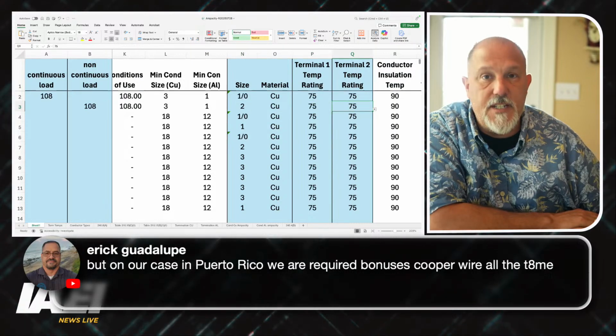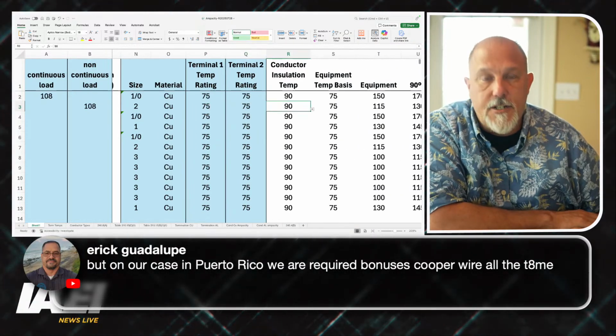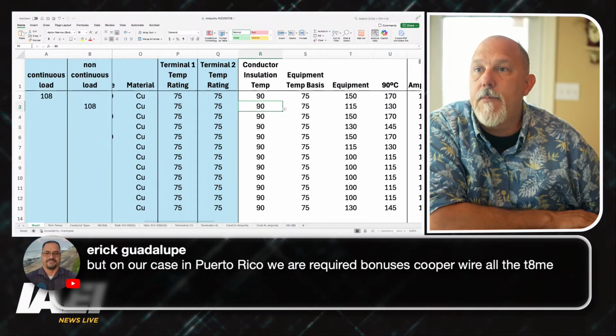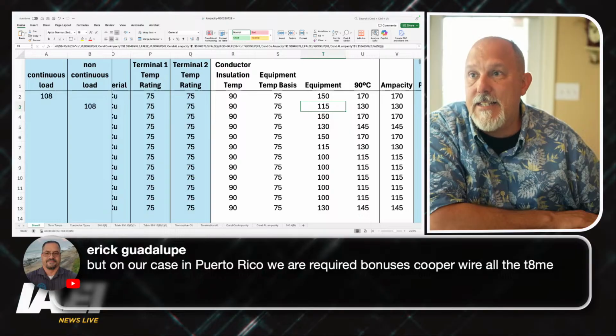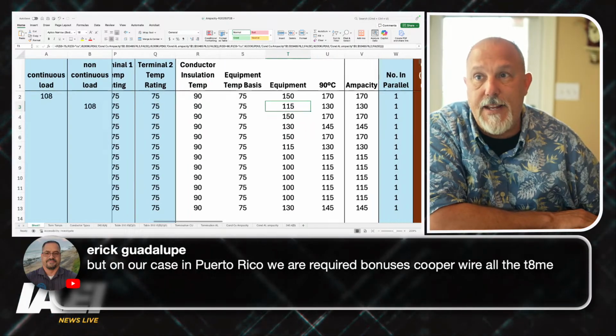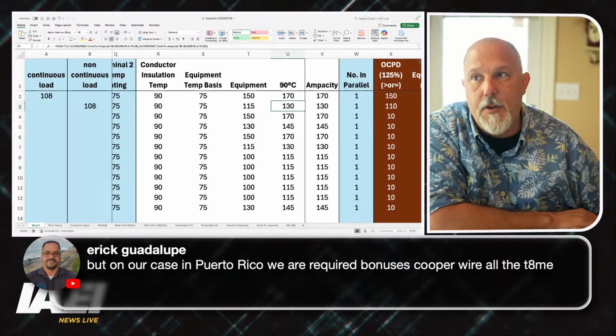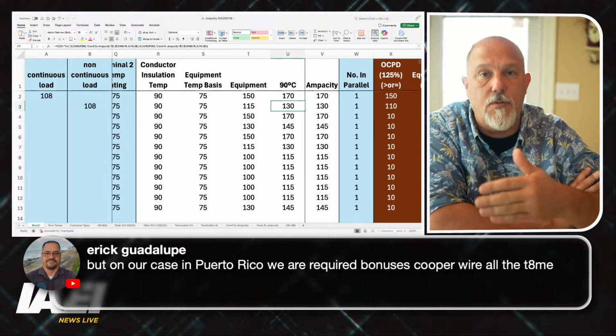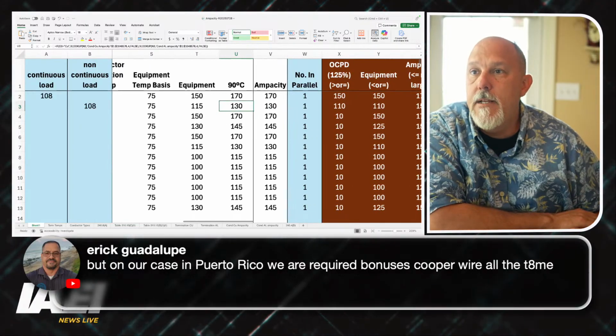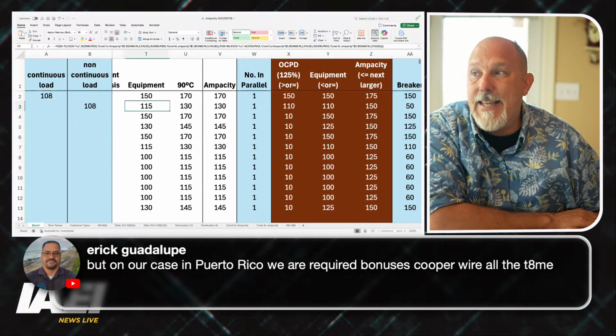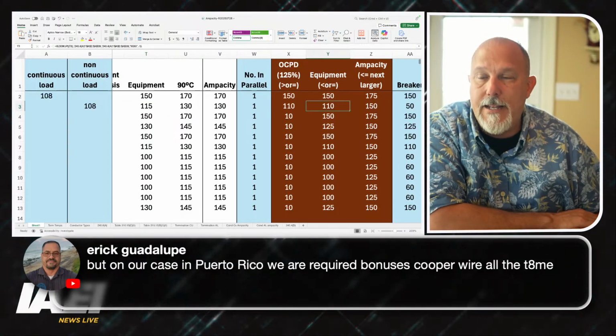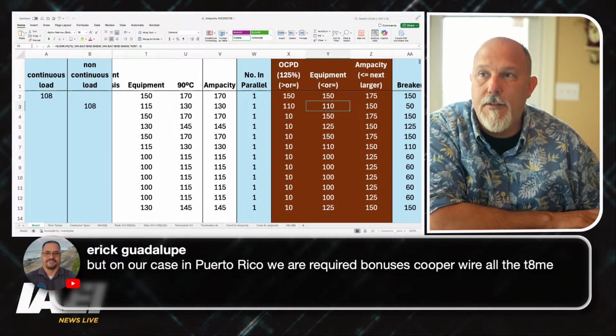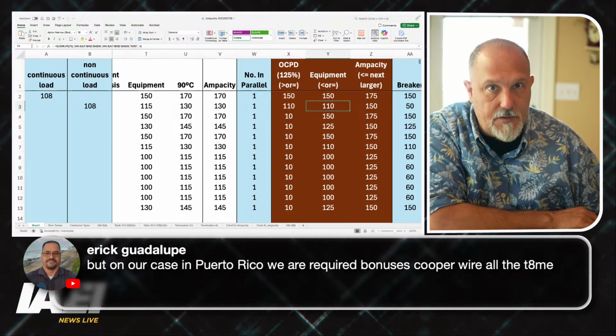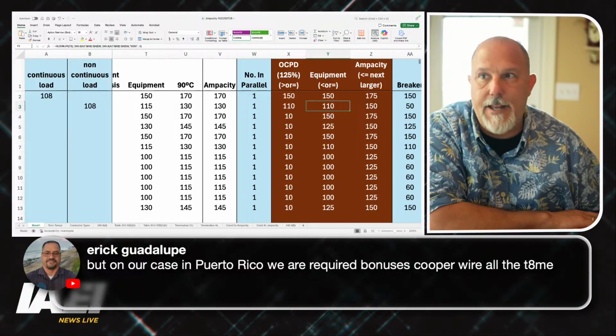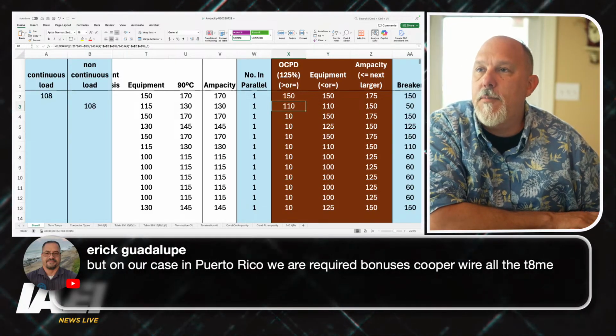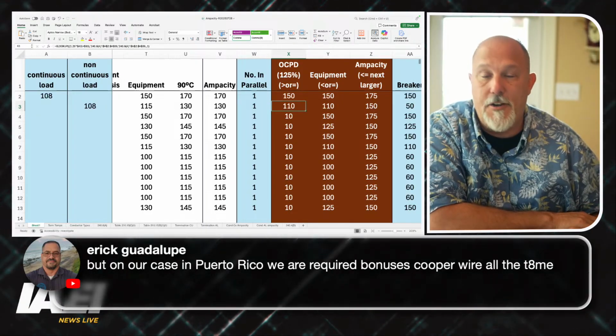My terminations are still going to be 75 degrees C. My conductor insulation is 90 degrees C. My equipment, based upon that size conductor, my overcurrent device can't exceed 115 amps. My ampacity is 130 amps. I can go to the next higher if it's not equal to a standard ampere rating. So, knowing that I can't exceed 115 on my equipment, I can't be greater than a 110 amp overcurrent protected device. So my overcurrent protected device has to be 110 or less.